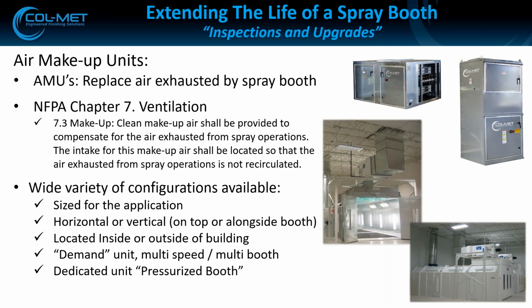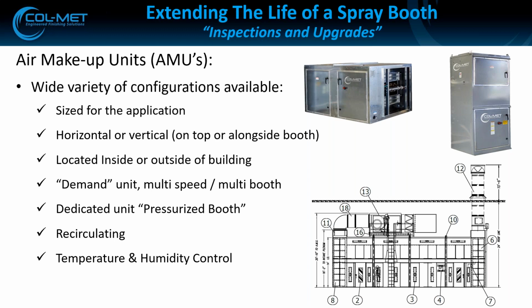The AMUs can be oriented probably any which way we need to make sure they fit your installation right. A lot of times an air makeup unit can be used just to dump into the building, and we call that a demand unit. If you had a woodworking shop that has 5 or 6 open front booths in there, you would set an air makeup unit up in there that just blew air into that environment. And when we know how many booths are running, then we know how fast to run the unit.